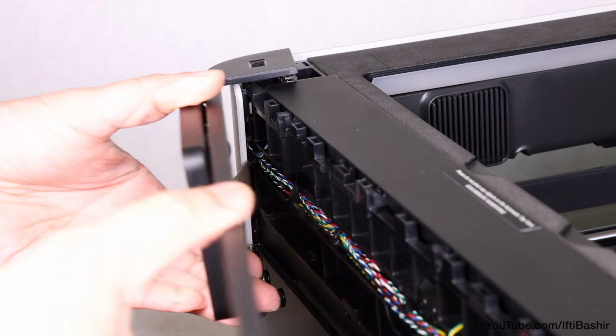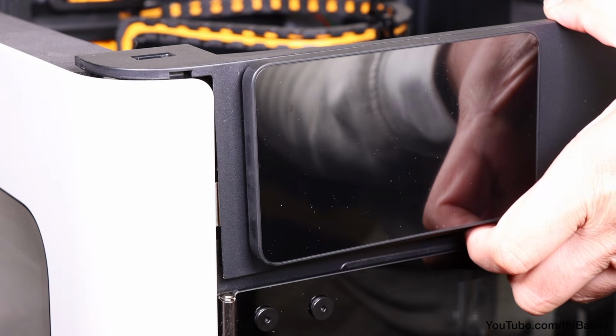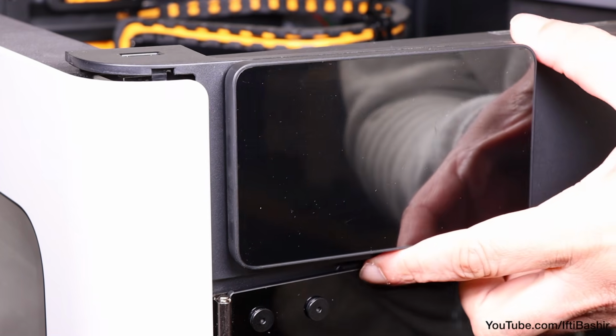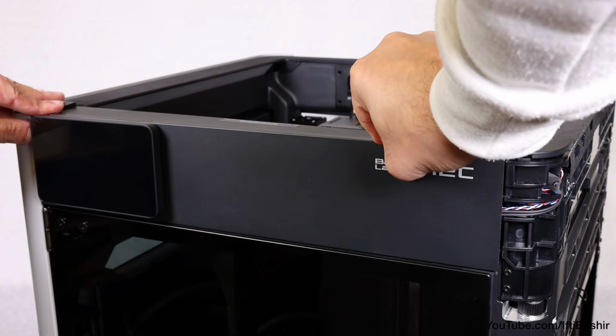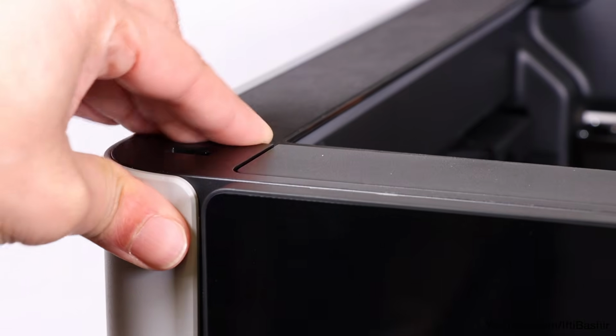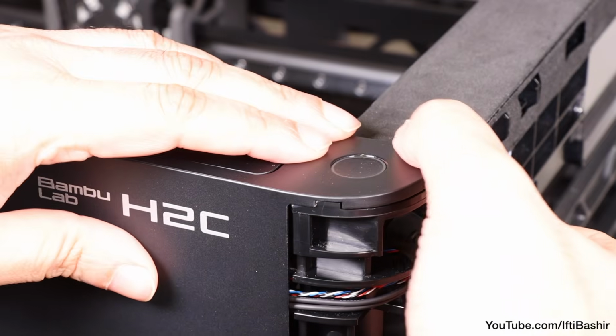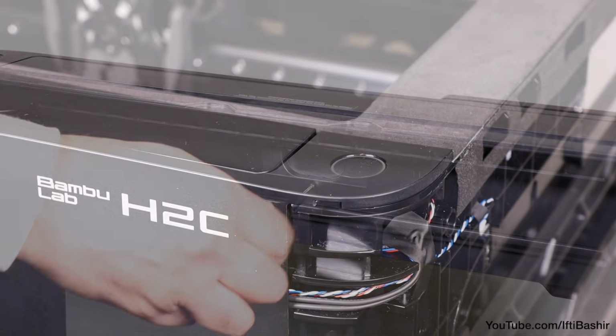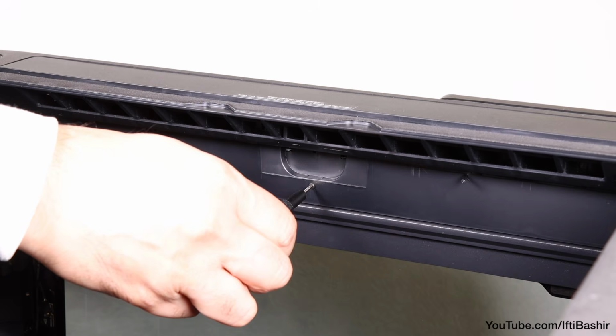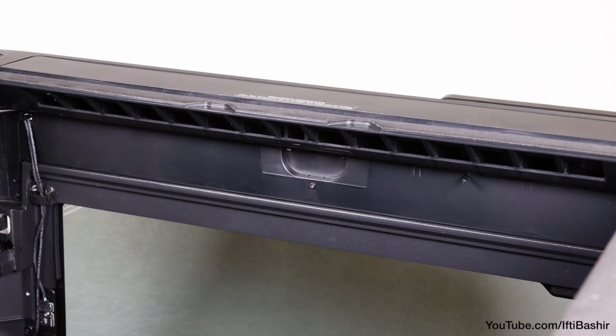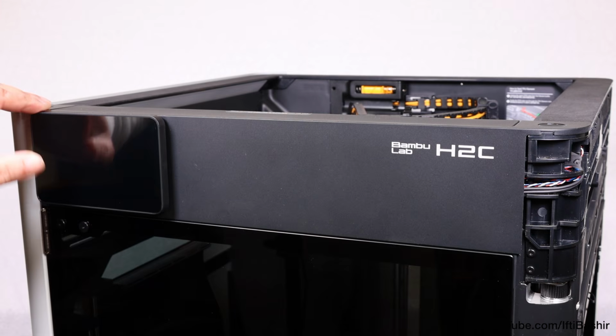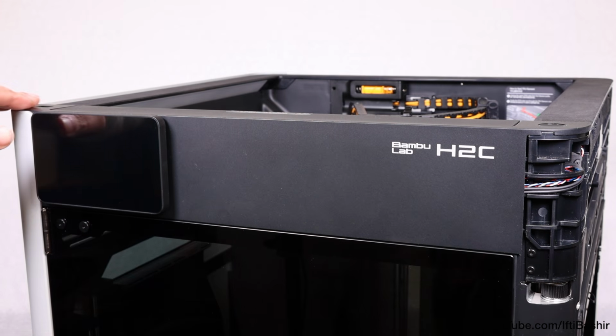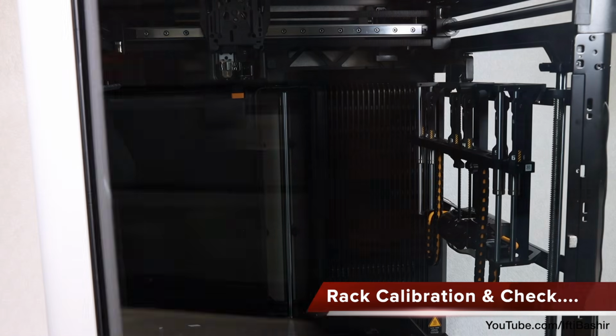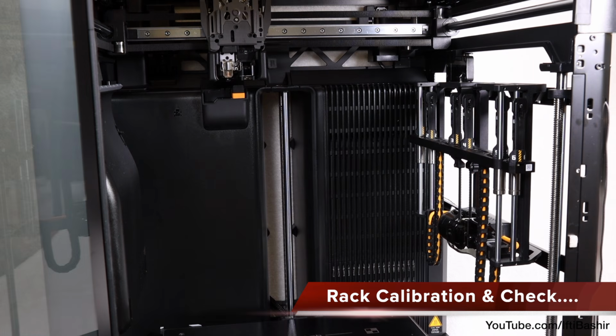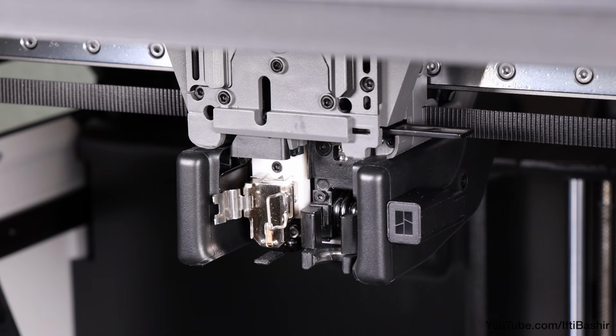All that's left then is to insert the left side of the front panel into the corresponding slot on the chamber, before pressing the front cover downward so that all clips are fully engaged into the frame slots. Finally, secure the single screw back into the rear side of the top middle frame. And with that, front panel replacement is complete. In fact, that's the entire Vortek upgrade complete at this point, so we're ready to run a quick check.